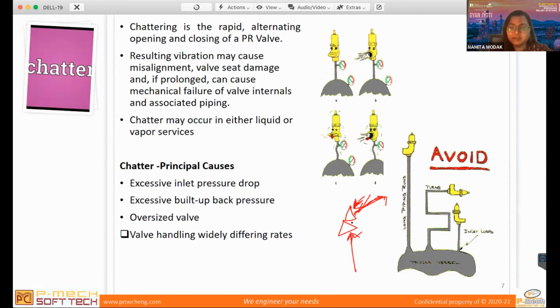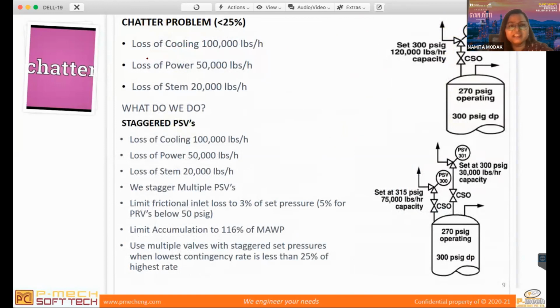And then the third one is oversizing. Oversizing means, let's say from my calculation the required orifice is D type, but if I select E type or F type, which is a higher size than what I required, then also chattering will happen. Normally this oversized valve, I'll show you a case where you can see oversizing happen. I have 3 scenarios applicable to this PSV. One is loss of steam, which requires 20,000. Then the loss of power scenario requires 50,000 lbs per hour, and the loss of cooling scenario requires 1 lakh lbs per hour. Now, in the example where I have selected a single PSV of a capacity of 120,000 lbs per hour, for loss of cooling it is adequate. But when it goes for loss of power or loss of steam, it is highly oversized.